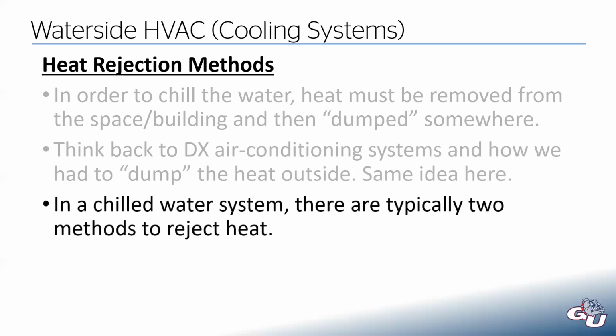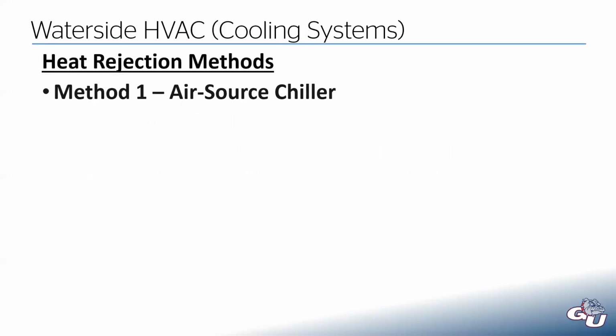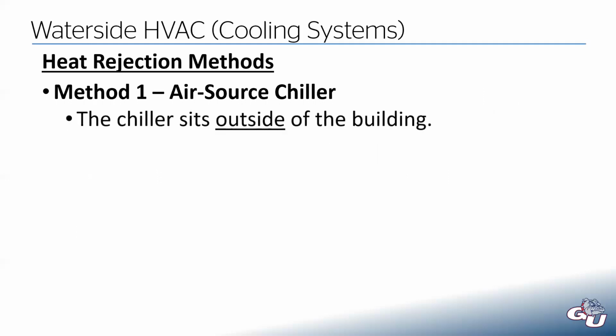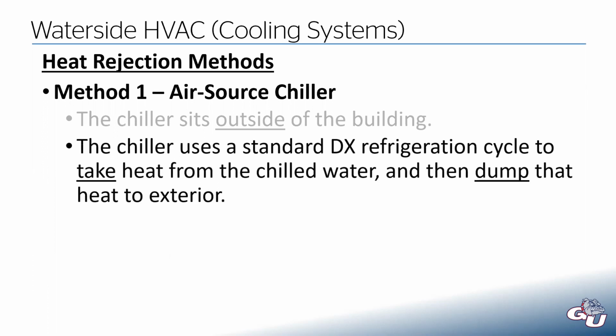And in a chilled water system, generally speaking, there are some caveats and specific changes to this, but fundamentally, there are typically two ways to reject heat in a chilled water system. The first method, and this is the, using air quotes, easy method, would be to use an air source chiller. I'll have a graphic here in a second that will help illustrate this, but the chiller that we're using to chill down our water stream sits outside of the building, and it has to sit outside the building. And then we're going to use a standard DX refrigeration cycle that will take heat from the chilled water and then dump that heat outside.